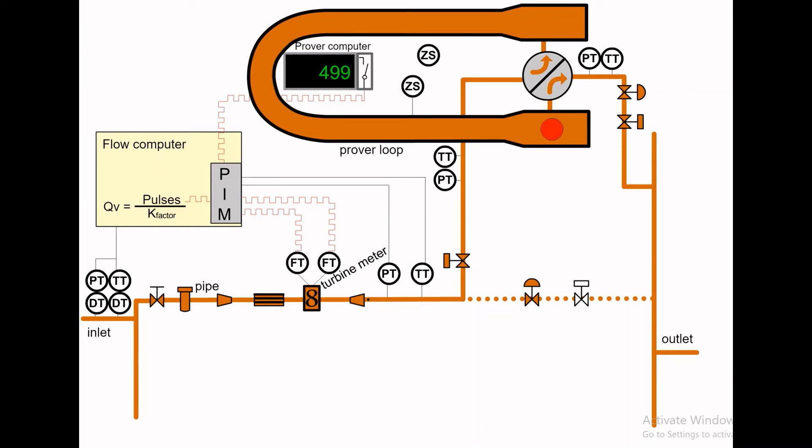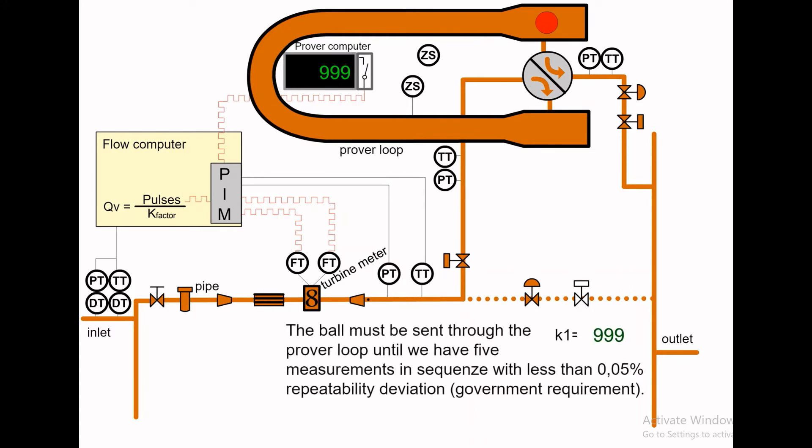The measurement must be taken for both directions, so the four-way valve is turned again. The ball must be sent through the prover loop until we have five measurements in sequence, each with less than 0.05% repeatability deviation. This is a government requirement.